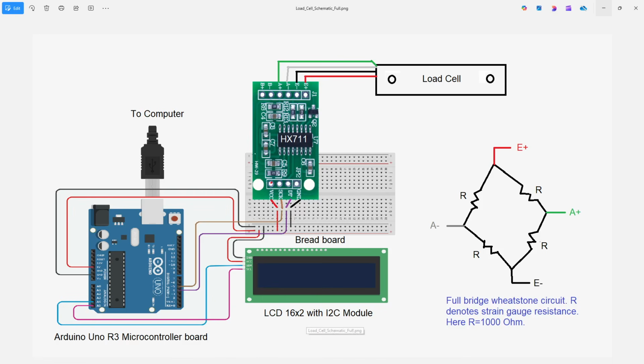I am going to walk you through the steps that are involved in carrying out the experiment on weight measurement using load cell. Let's first start with the circuit diagram for this problem. What we have is a bar type load cell. The load cell is fixed at one of the ends and the force is applied through the other end. This is a 5 kilogram or 5000 grams rated bar type load cell.